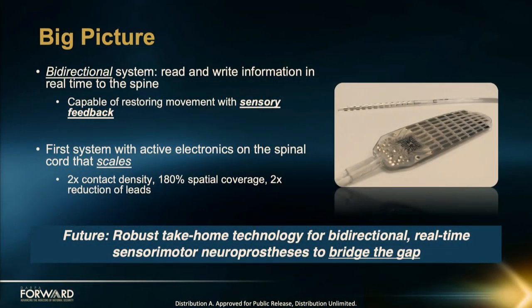For a big picture of what we're doing: we are building a bidirectional system into the nervous system through a leap in our technology. We built electrode arrays that interface with the spinal cord. The state of the art today is a 32-channel system from Boston Scientific, which has four big pigtails coming out the back. Our new HD64 system has an ASIC built onto it — a multiplexer — allowing us to connect to 64 channels right now, with the system scaling to many more, and only two cables coming out. That's really important as we build toward next-generation interfaces to the nervous system. I'll thank my entire team for all this work — thank you very much for listening.